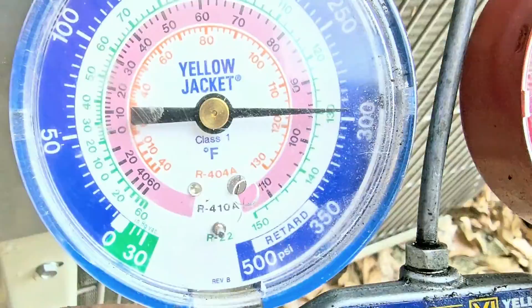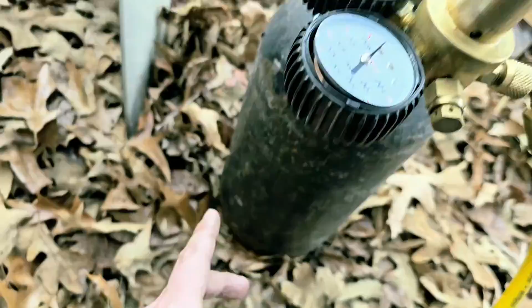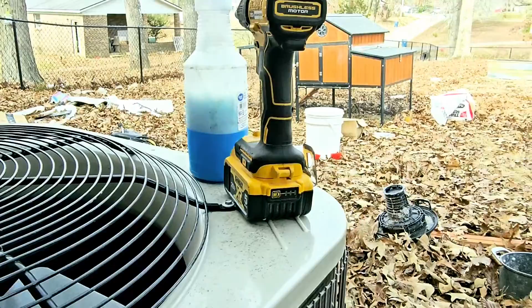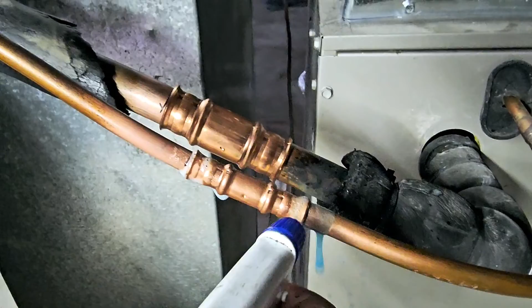Let's go. We got about 300 pounds of pressure on the system, and this is pressure nitrogen inside the line sets and the indoor coil. So that's my nitrogen tank and my regulator. And now I'm going to get the soap bubbles and go inside. And make sure there's no leaks. And then put some new insulation on there.